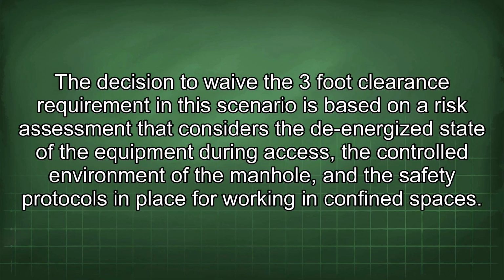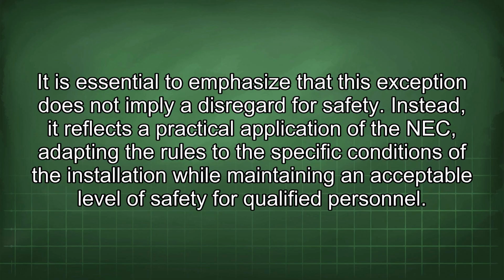The decision to waive the 3-foot clearance requirement in this scenario is based on a risk assessment that considers the de-energized state of the equipment during access, the controlled environment of the manhole, and the safety protocols in place for working in confined spaces. It is essential to emphasize that this exception does not imply a disregard for safety. Instead, it reflects a practical application of the NEC, adapting the rules to the specific conditions of the installation while maintaining an acceptable level of safety for qualified personnel.